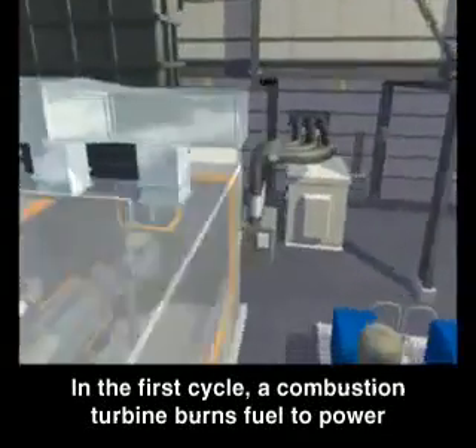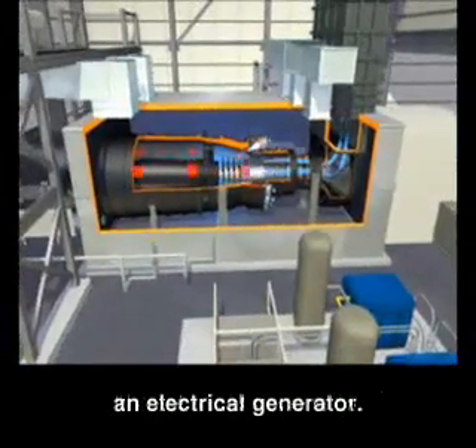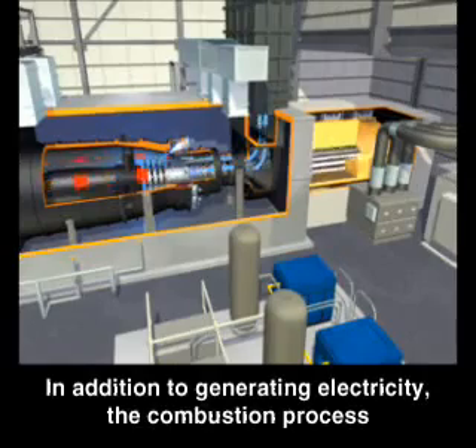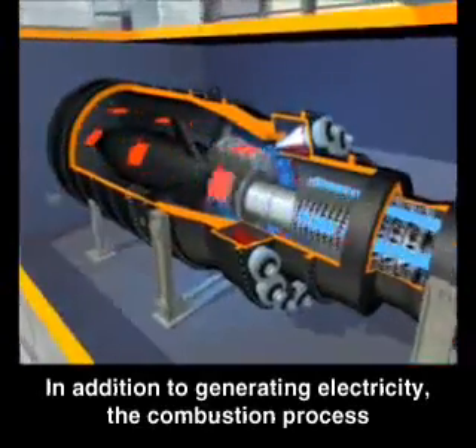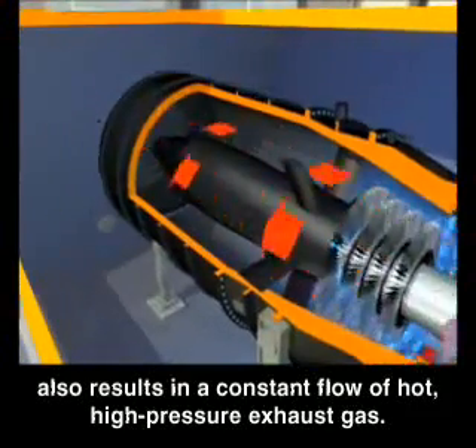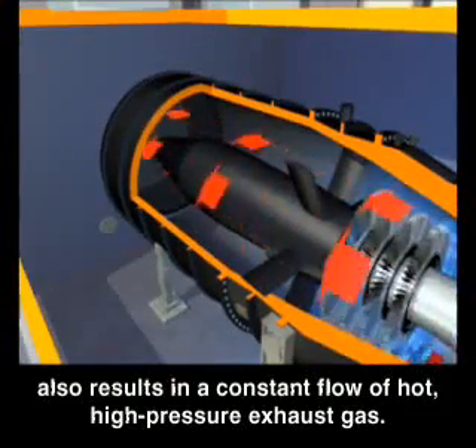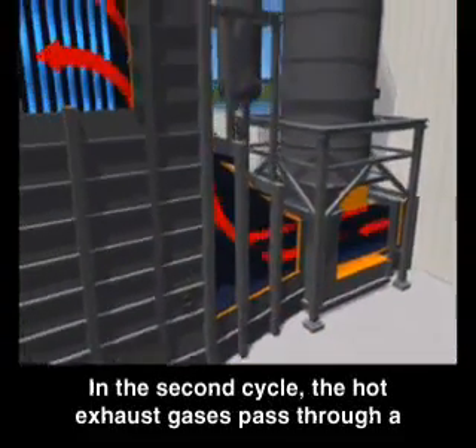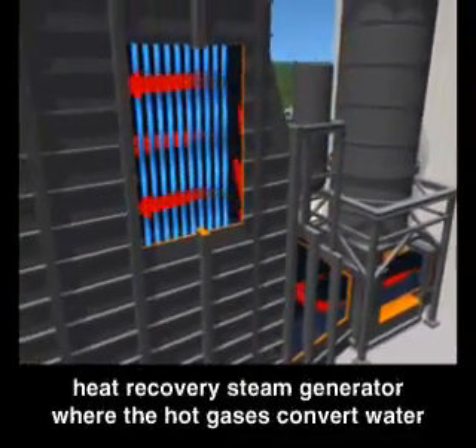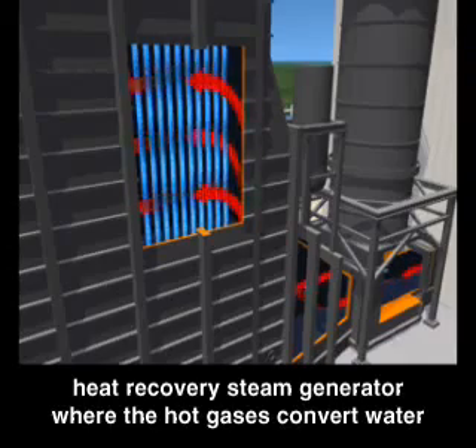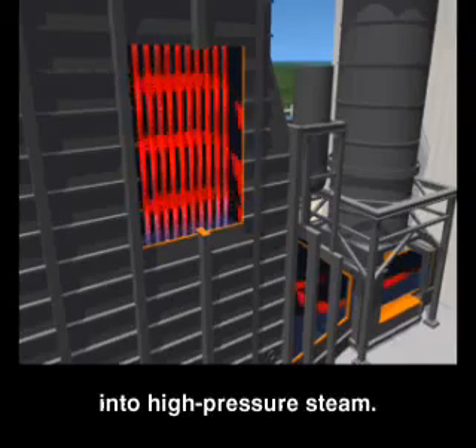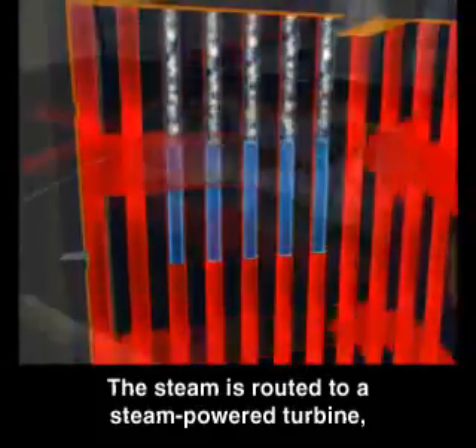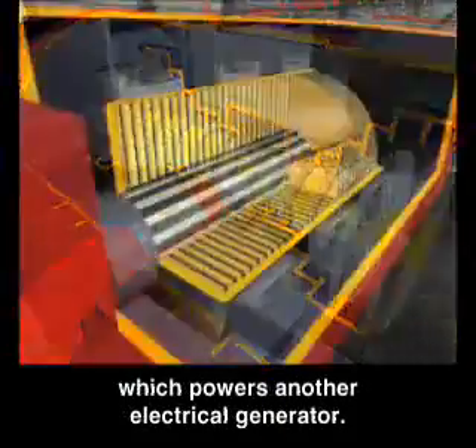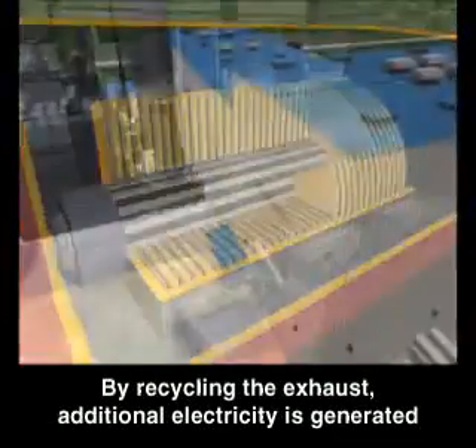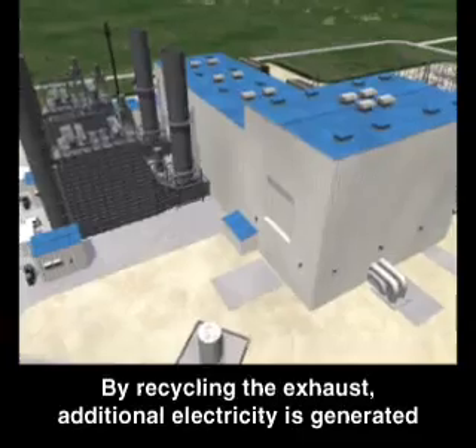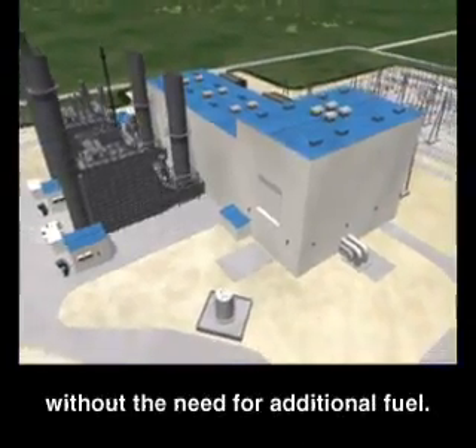In the first cycle, a combustion turbine burns fuel to power an electrical generator. In addition to generating electricity, the combustion process also results in a constant flow of hot, high-pressure exhaust gas. In the second cycle, the hot exhaust gases pass through a heat recovery steam generator, where the hot gases convert water into high-pressure steam. The steam is routed to a steam-powered turbine, which powers another electrical generator. By recycling the exhaust, additional electricity is generated without the need for additional fuel.